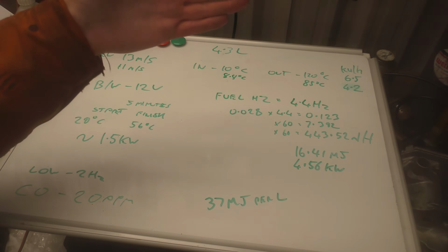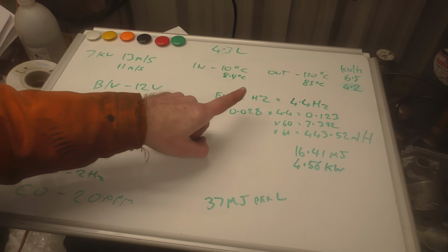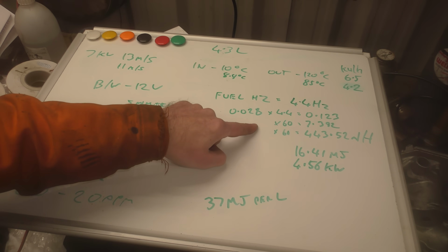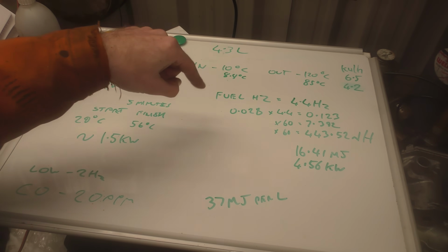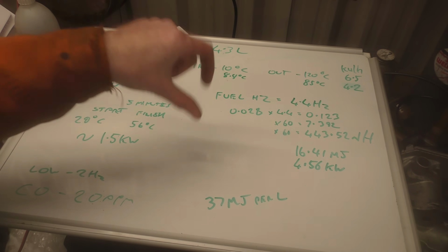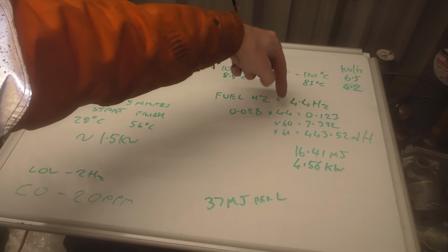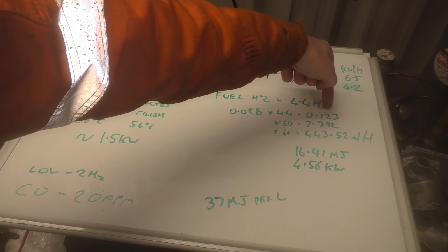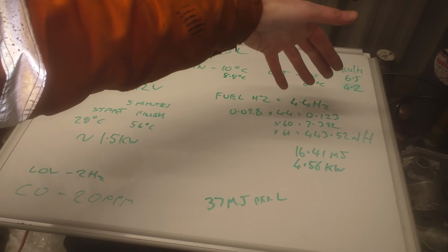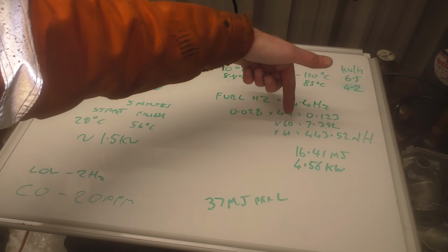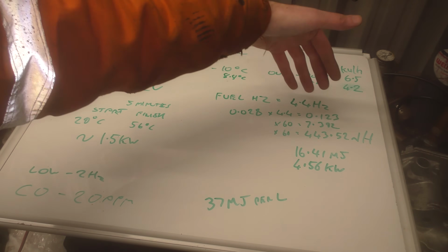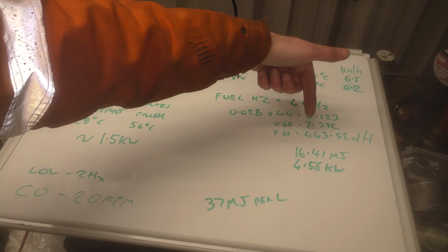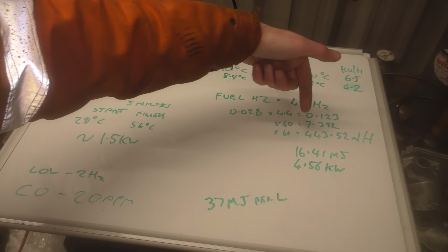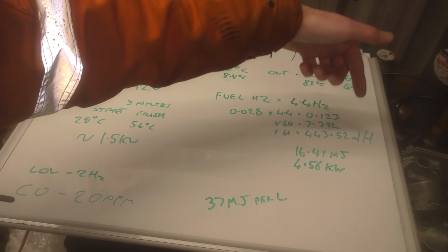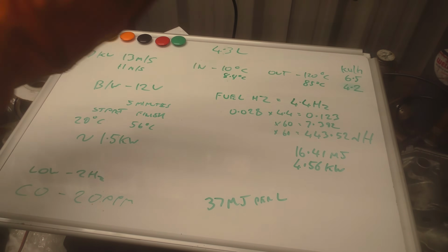So that pump is doing 4.4 hertz. It's a 28 mil pump, so that's 0.028 milliliters per stroke. Times that by 4.4 gives 0.123 milliliters per second, times that by 60 gives 7.4 milliliters a minute, and times that by 60 again gives 443.5 milliliters an hour.